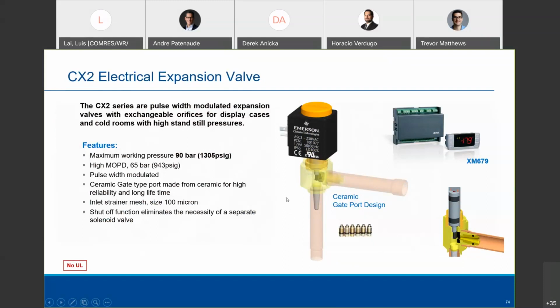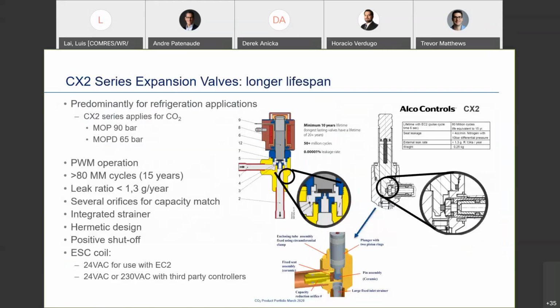One of the things with pulse width modulated valves is as these valves modulate up and down, like you see here, 1 pulse per period of 20 seconds or 10-second period, there's sometimes a clicking noise that's annoying to customers. So the White-Rodgers team is trying to dampen that noise when it opens and possibly resurrect the new PWM. So there's a project underway with that for North America.